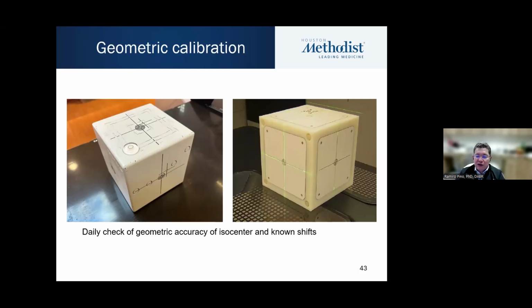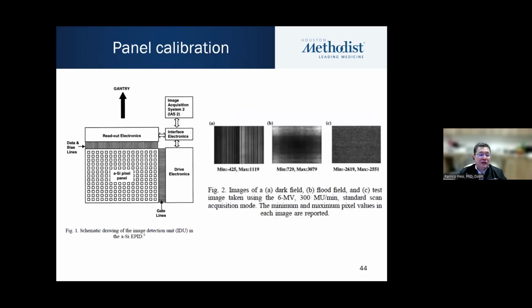These are two examples of phantoms that can be used to check geometric accuracy of isocenters and known shifts, and this could be used both for kV or MV image guidance, both planar or 3D imaging. The panel needs to be calibrated periodically depending on manufacturer specs, and typically you have a dark field, which is basically the background noise, and you have a flood field, which basically measures the sensitivity of your detectors, and then you apply corrections.